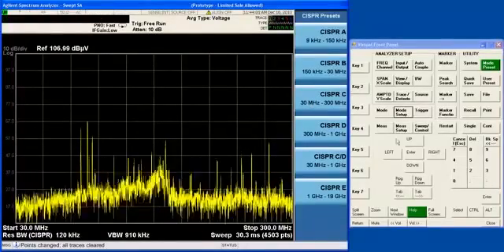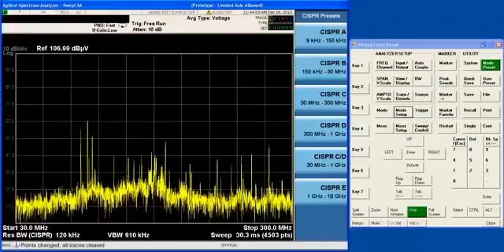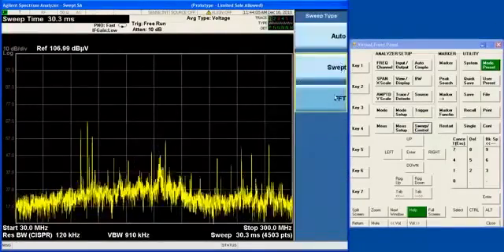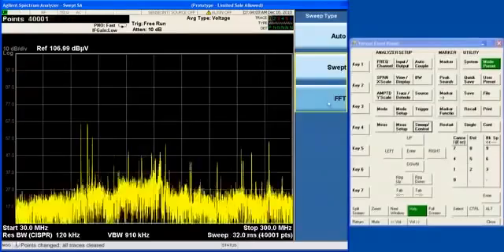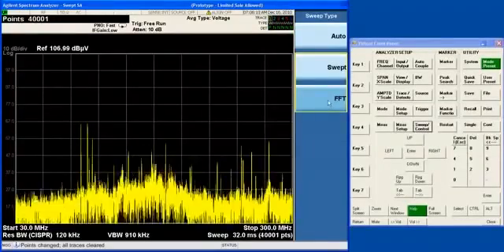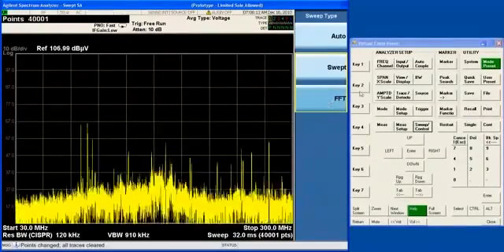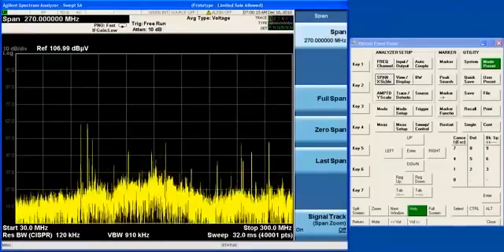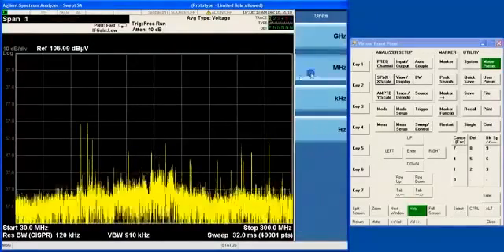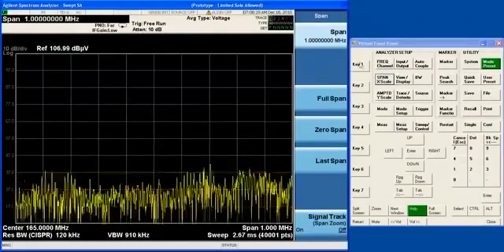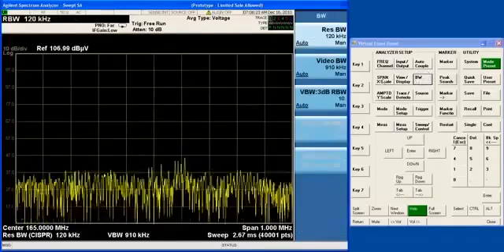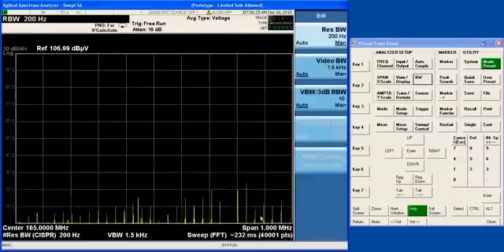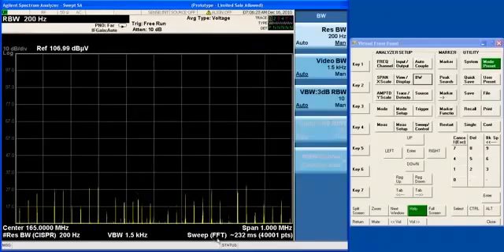Besides the swept mode of the analyzer, all X-Series analyzers also have FFT sweep modes, which the analyzer will automatically choose if you get into a narrow bandwidth. For example, if we were sweeping over a narrower span, say 1 MHz, and we lowered the resolution bandwidth to say 200 Hz, you can see that it automatically switches into the FFT sweep mode.